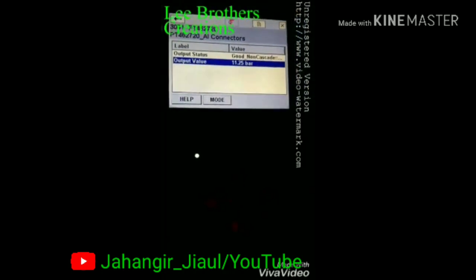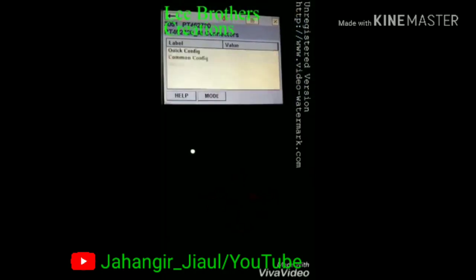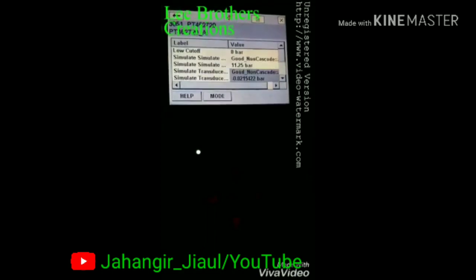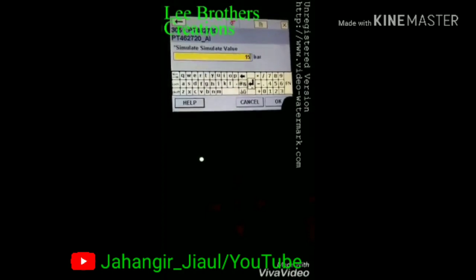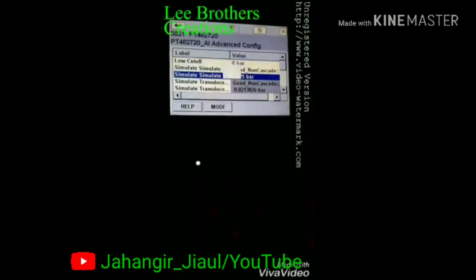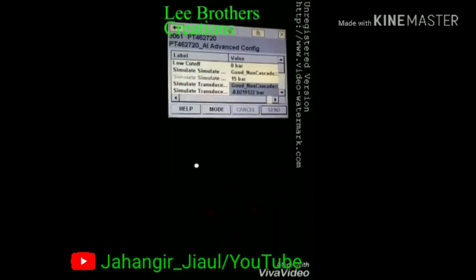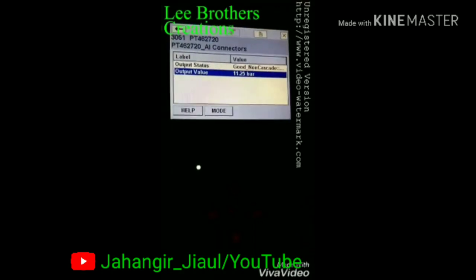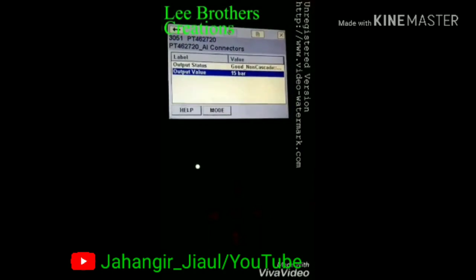Now I enter the 75% value and click send. Next I want to set 100%, which is the maximum range — URV, meaning upper range value. I enter that value: 15 bar. Click send, come back and go to the DCS connector. The DCS side will show 15 bar.